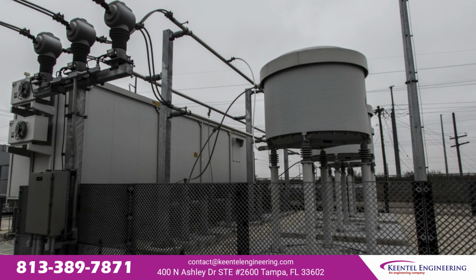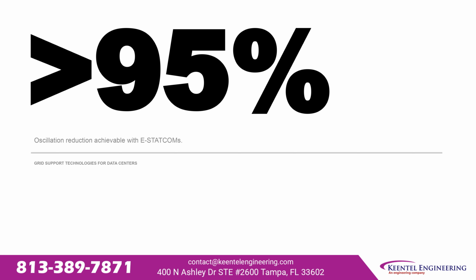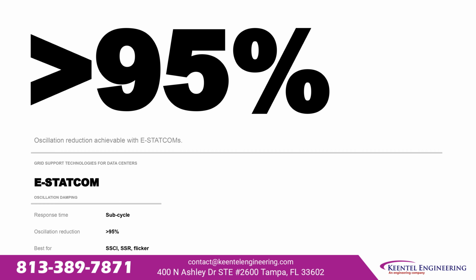3 technologies address the grid impact of AI data center loads. E-STATCOM for oscillation damping. Sub-cycle response time, greater than 95% oscillation reduction, best applied for SSCI, SSR, and flicker. That 95% figure is the headline. When SSCI is confirmed, E-STATCOM is the mitigation.